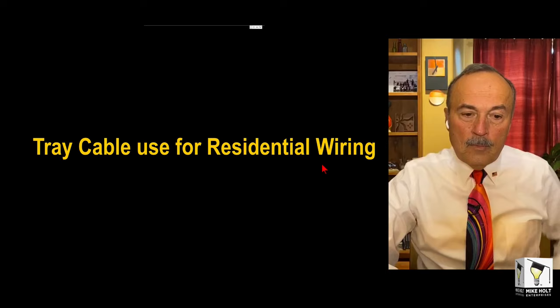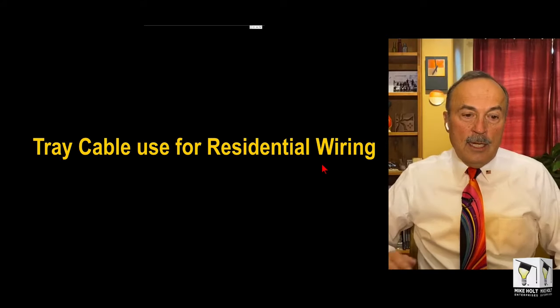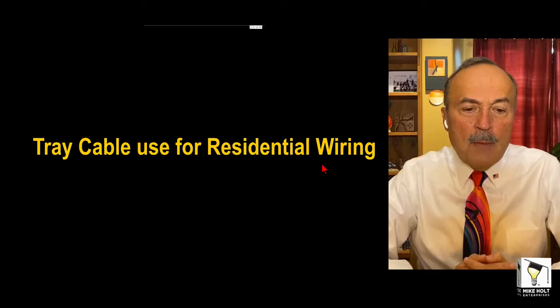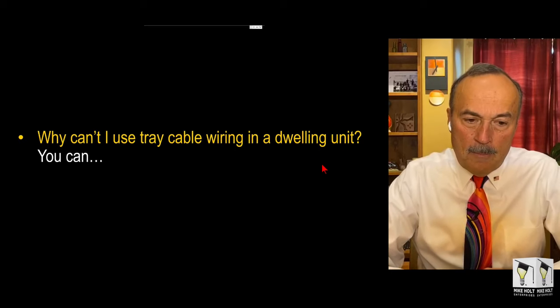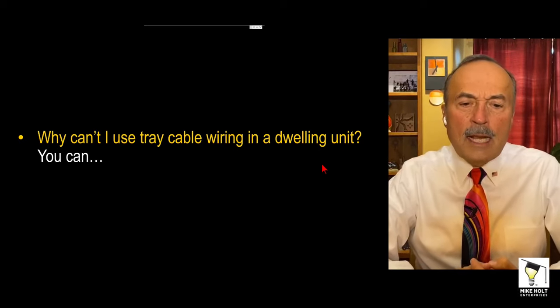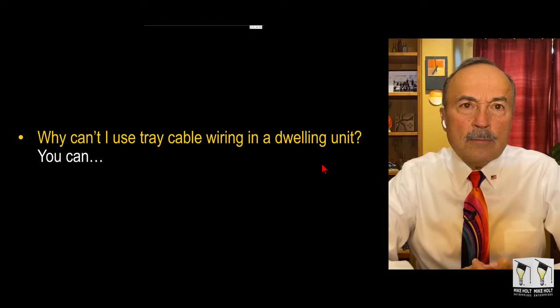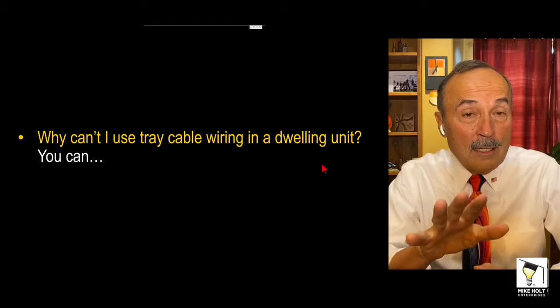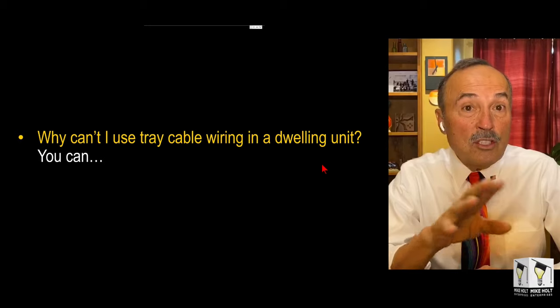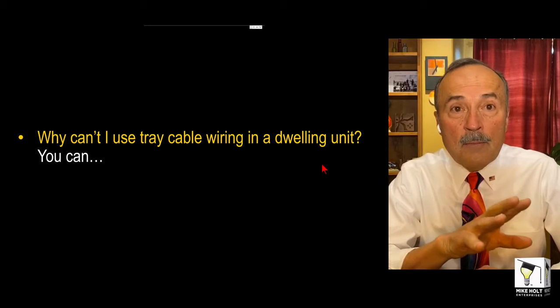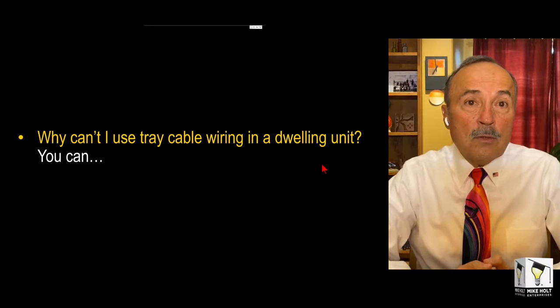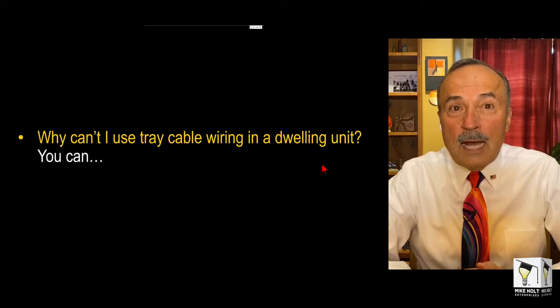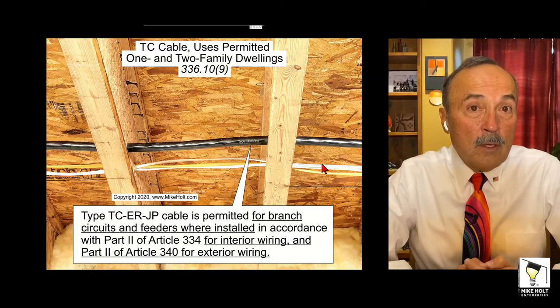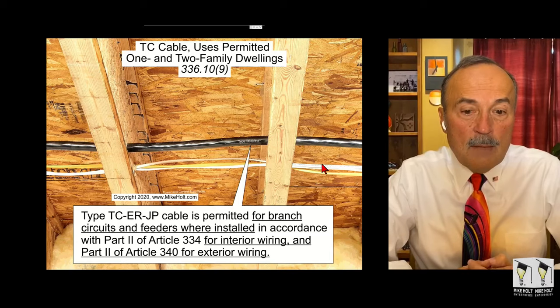Okay, let's move on. One light question, and then we're going to finish up. Tray cable use in residential wiring. He says, "Mike, why can't I use tray cable wiring in a dwelling unit?" I'm like, well, you can, but that depends on the code that you have. For all time, tray cable, or type TC wiring, was not permitted in a lot of locations where it is today. So that's Article 336. Tray cable, type TC cable.